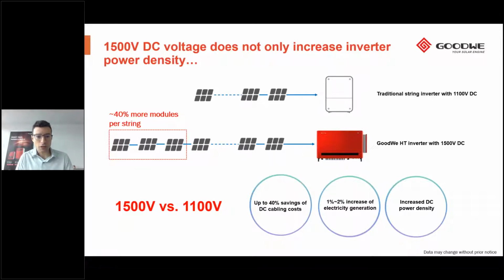And Josephine mentioned earlier about this increasing and also becoming a de facto standard in the utility scale industry with very high market shares. And this 1500 volt DC voltage does not only increase the inverter power density, but it also brings benefits for the power plant overall. And what you see here in this slide, in this schematic overview, if you compare a traditional string inverter with 1100 volt DC technology with the inverter HT series with 1500 volt DC technology, the EPC is able to put up to 40% more modules per string, and this reduces up to 40% the DC cabling costs.